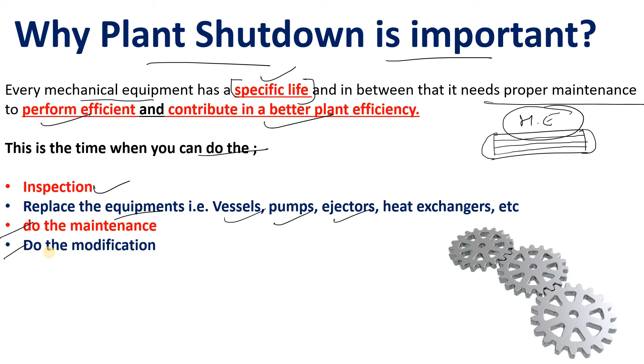Got my point? And this is the time when you can do the inspection of the equipment. You can replace equipment like vessels, pumps, ejectors, heat exchangers, any mechanical device, control valves. You can do some modification at that time. Suppose there is a retubing, you can do the retubing in the heat exchangers. That is the time when you can do the maintenance and the modification. That is the best time to do everything to improve the plant efficiency. That is why this plant shutdown is important.